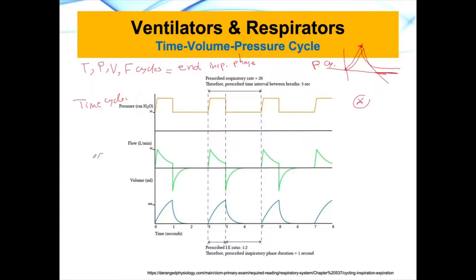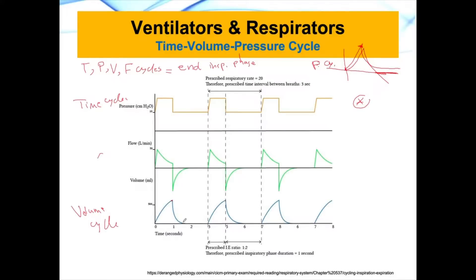We also have something called volume cycle. The blue line at the bottom is an example of a volume cycle. What happens is that you are increasing the volume of the air flowing into the lungs to a certain point, and when it reaches that specific volume in milliliters, you stop the inspiratory phase and allow the expiratory phase to take place. That's volume cycle, volume controlled.